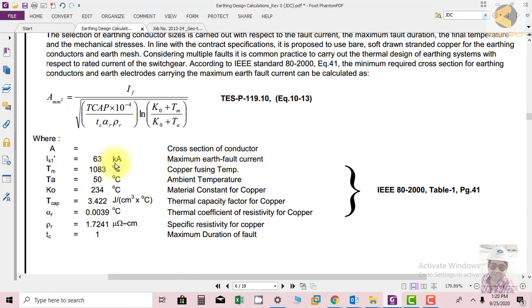Here is the cross section of conductor that we have to use in a mesh. IK1 is maximum earth fault current. This current is maximum fault current and is provided by the utility or it can also be calculated.